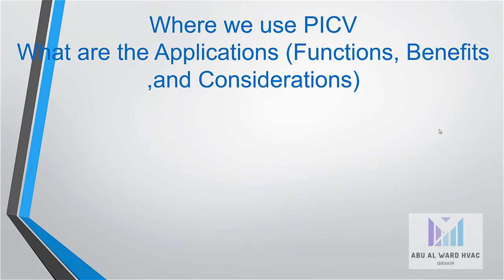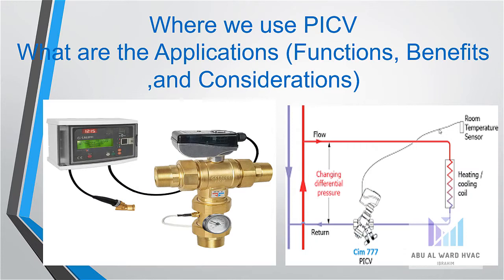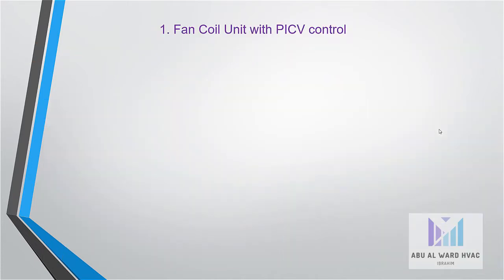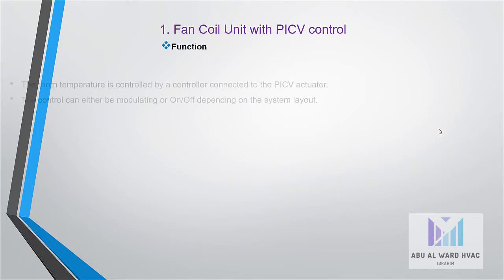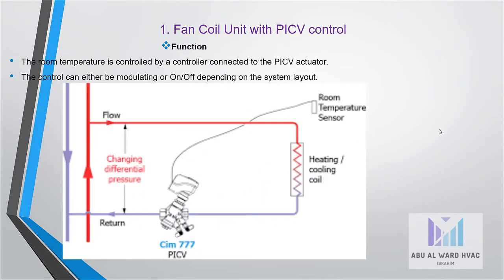Where do we have to use this PICV, and what are the applications, functions, benefits, and considerations? Number one, we can use it in the fan coil unit with PICV control. The function: the room temperature is controlled by a controller connected to the PICV actuator. The control can be either modulating or on-off, depending on the system layout.